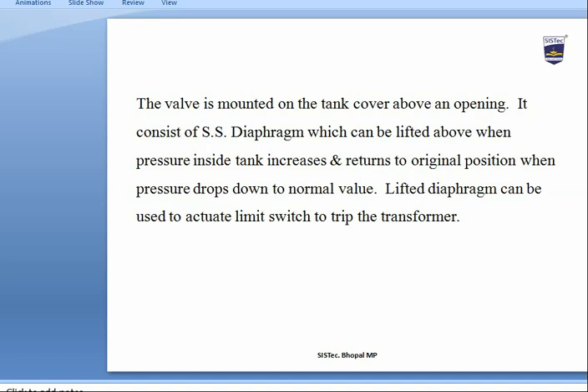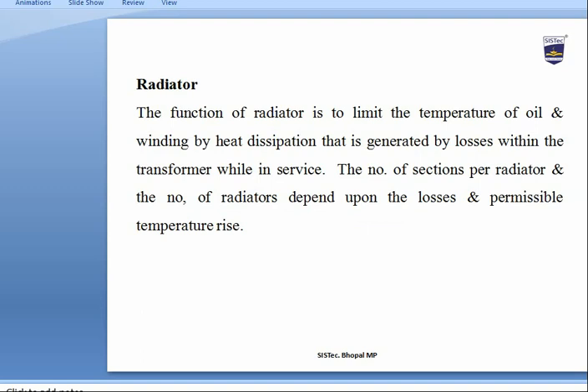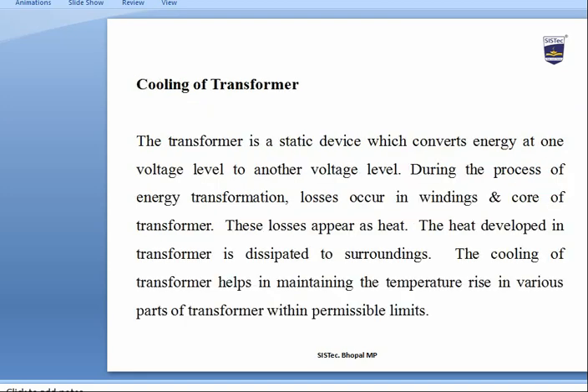The lifted diaphragm can actuate a limit switch to trip the transformer. The function of the radiator is to limit the temperature of oil and winding by heat dissipation generated by losses within the transformer. The number of sections per radiator and the number of radiators depend upon the losses and permissible temperature rise.